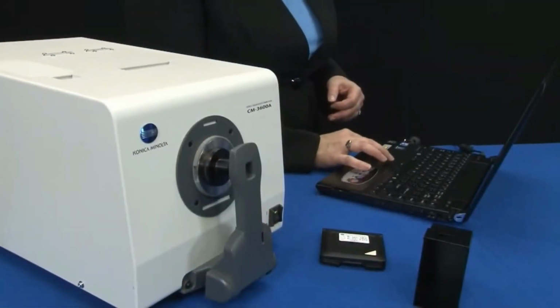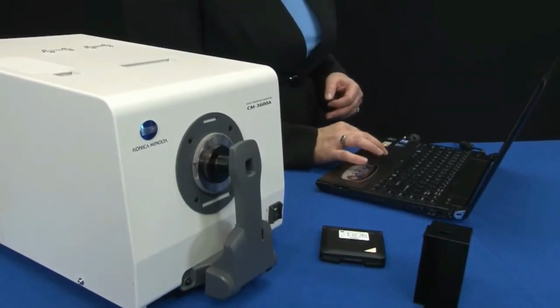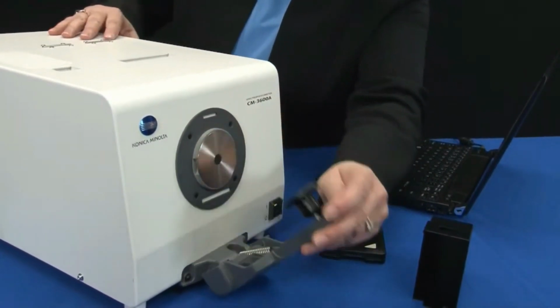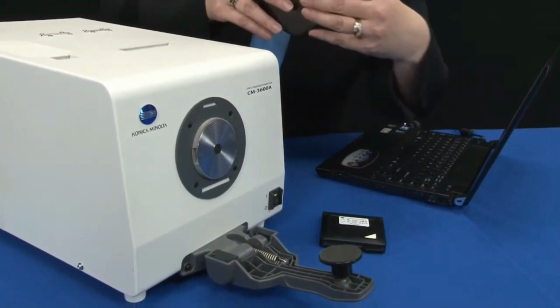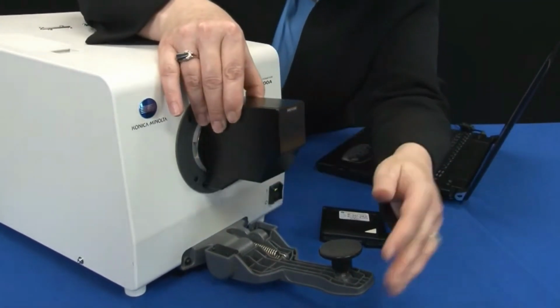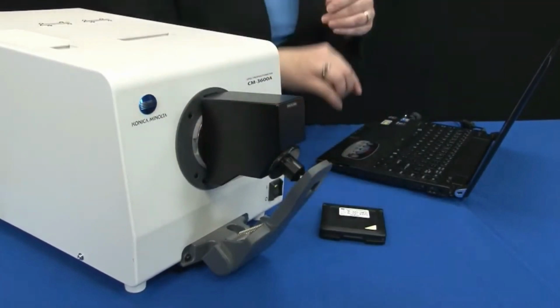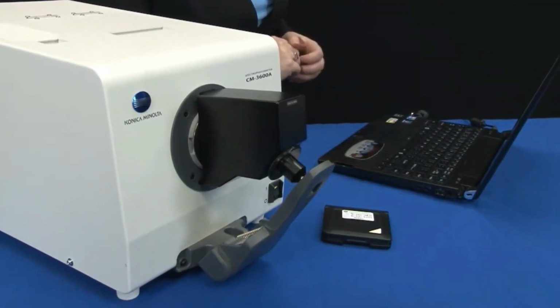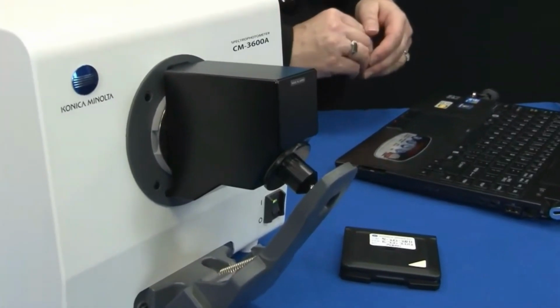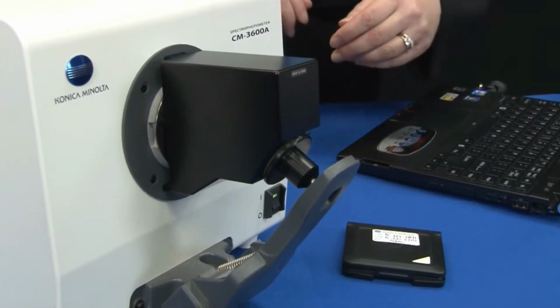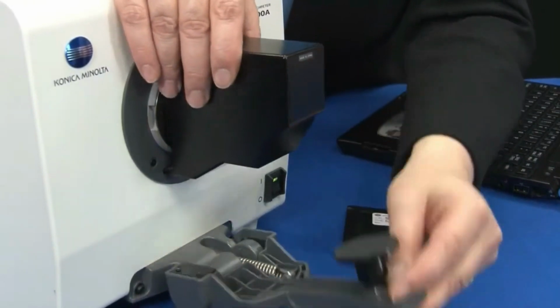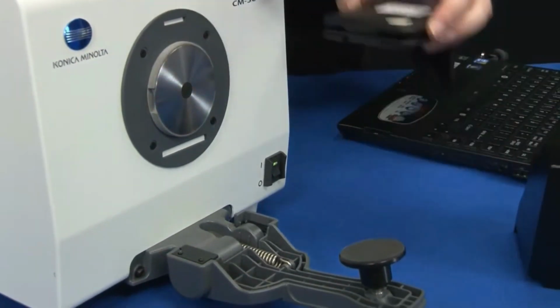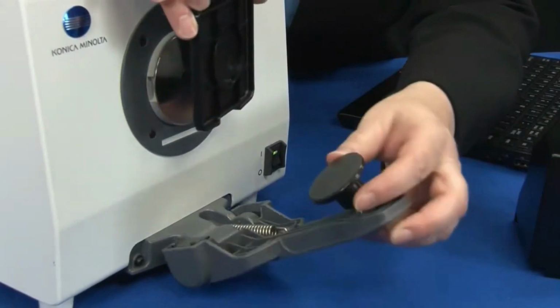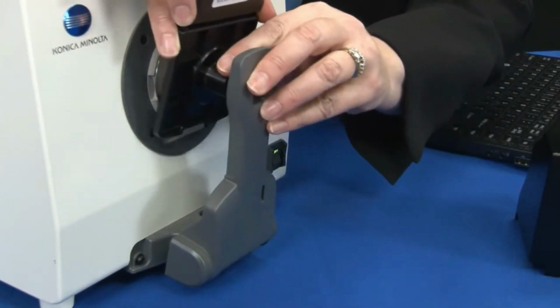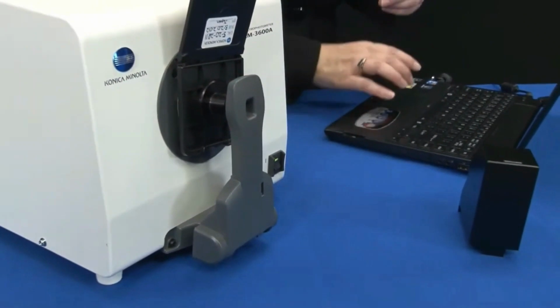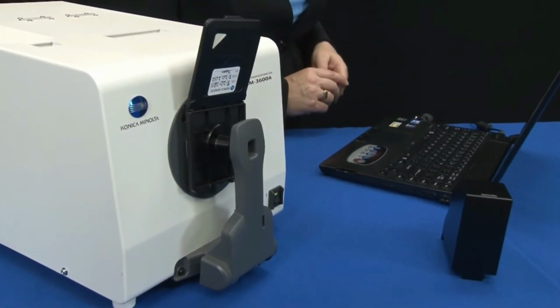The procedure for daily calibration for a Konica Minolta color measurement instrument is simple and straightforward. Two measurements are taken with the instrument. The black measurement, referred to as a zero calibration, can be performed by utilizing a special attachment for the instrument which absorbs all light. This is referred to as a zero calibration box. The next measurement is with a ceramic white standard with traceable values. The measurement of the white ceramic standard must always be performed with the standard that was assigned to the instrument. Each white standard has a serial number and is easily paired with the correct instrument.